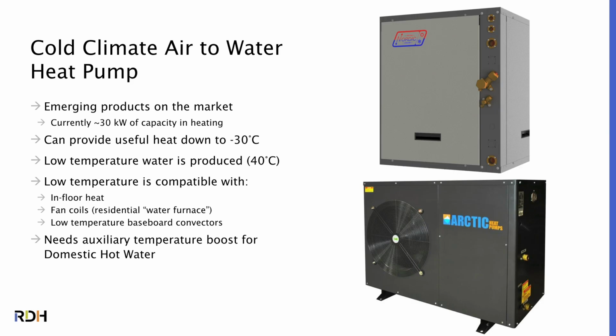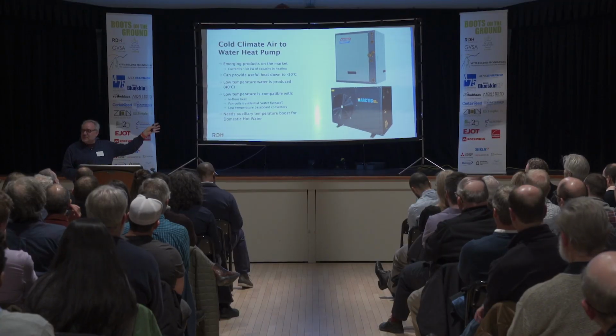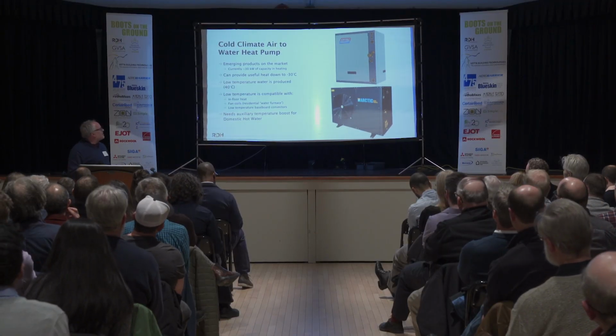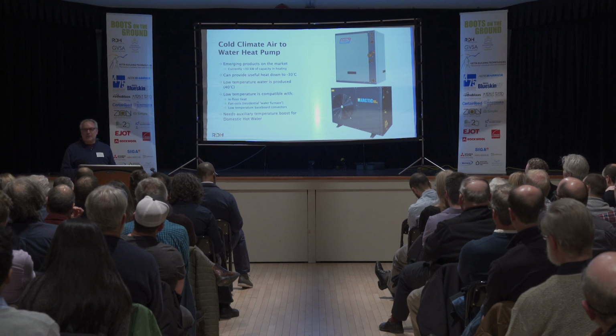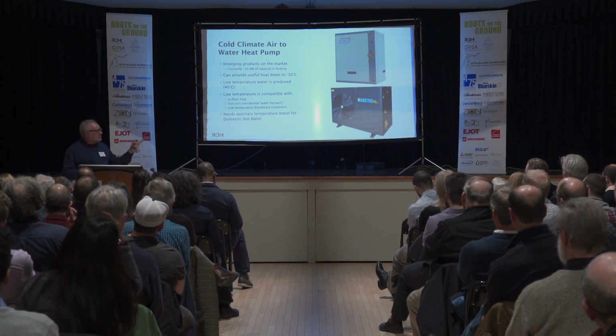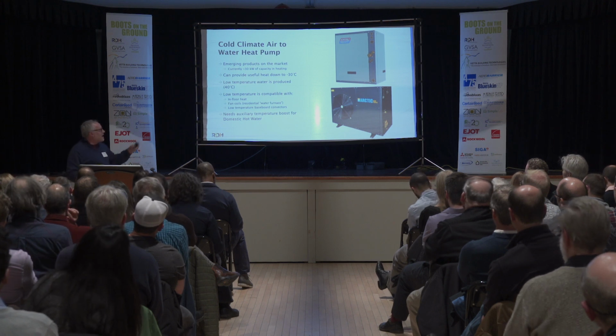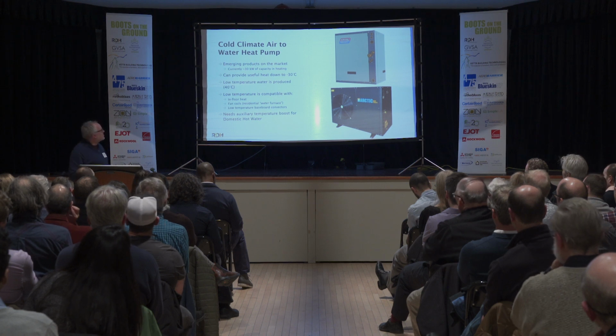We are starting to see cold climate air to water heat pumps arrive. They're just starting. They're both from the Maritimes. I don't know what's going on in the Maritimes. One is in New Brunswick and the other one is in Nova Scotia. They're good for about 30 kilowatts. So if you're thinking of a MURB, a small MURB, you could probably do maybe 4 or 5 of these to do 50, 100 suites or something.